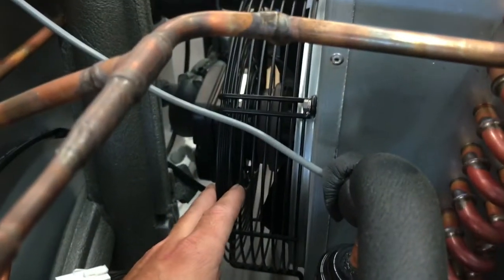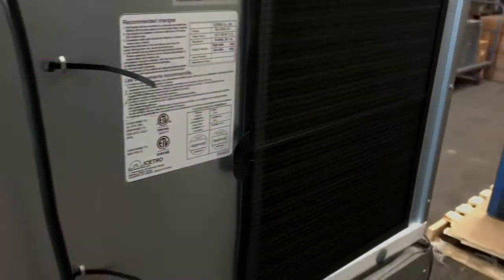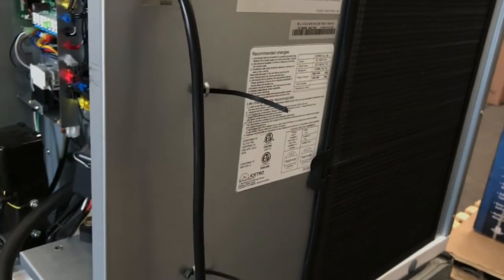It could be that your condenser fan motor isn't running, which you're going to notice right away. It could be that you've got a clogged air filter, and so you're not getting air across that condenser. How many times on air conditioning calls do you hear about clogged air filters? Well, I'm sorry, that wouldn't be the case on an air conditioning system, because your air filter is for your indoor air, not your outdoor air.